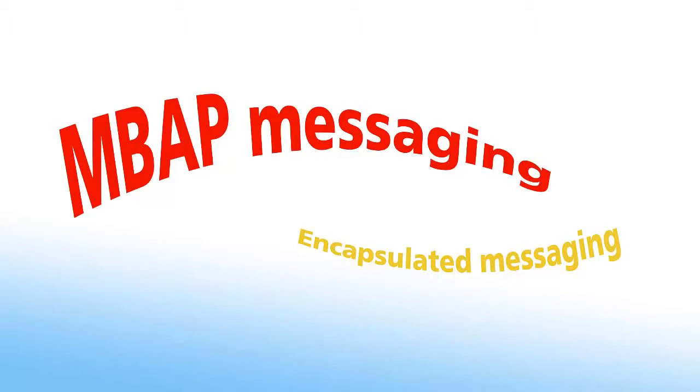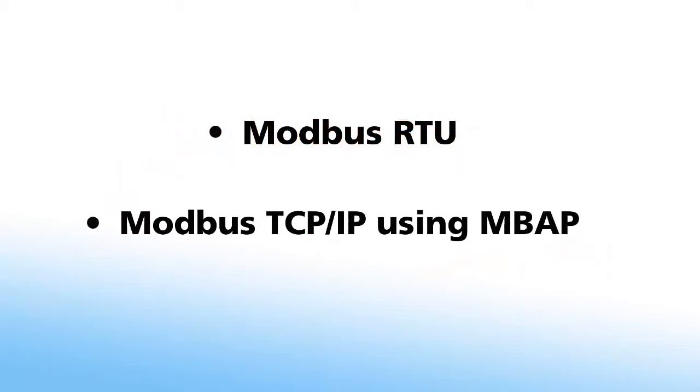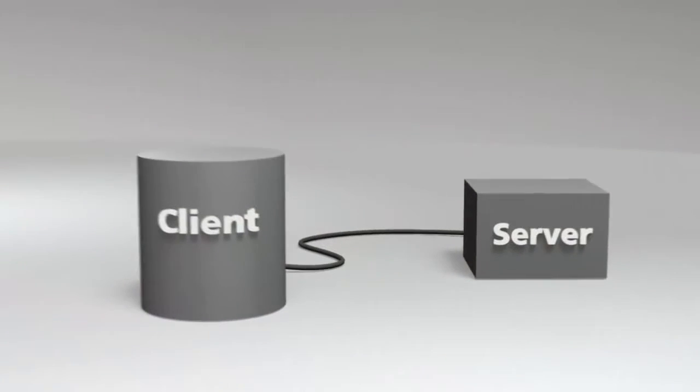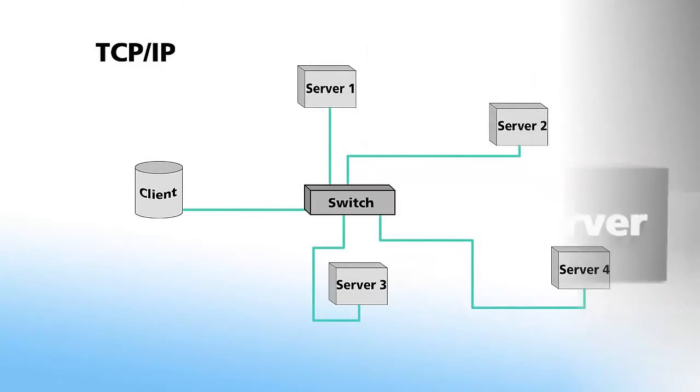MBAP messaging is by far the most popular Modbus TCP IP communication method. So for this video, we'll be focusing on Modbus RTU and Modbus TCP IP using MBAP. Modbus TCP IP uses the terms client and server instead of master and slave. The TCP IP network consists of the client connected to a switch or a series of switches to which all the servers on the network are also connected.